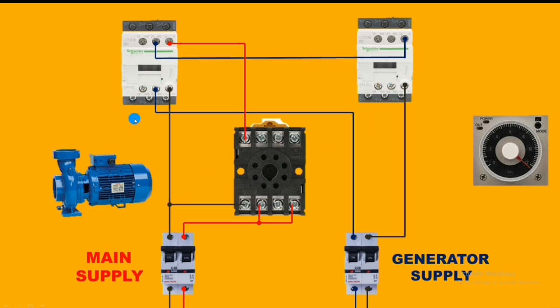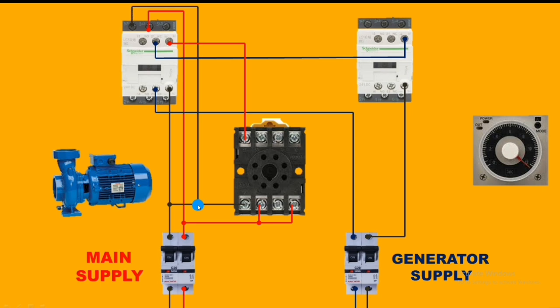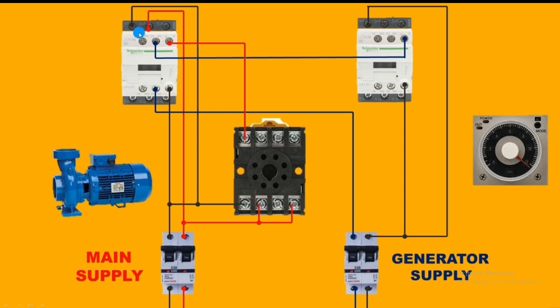Now for the power wiring connection: in the main contactor, connect the line from the main power supply to the L2 terminal — you can use any terminal. The neutral wire from the main power supply connects to the L1 terminal. For the generator power supply, same wiring: neutral connects first to the L1 terminal — the terminal should be the same as in the main contactor. Then the line from the generator or inverter power supply connects to the L2 terminal.